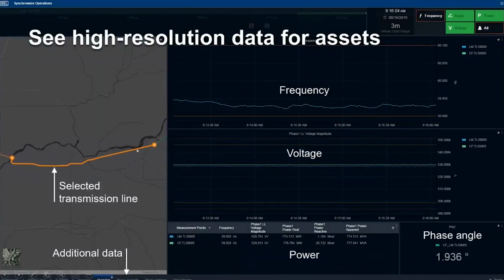So you can see that once I click on that asset, it's giving me the frequency, the voltage, the power, the phase angle, and any other information that I desire. Any information that the relay provides me, I can get that same information from this software. And again, it's in real time, it's in high resolution, so you can get much more information from this software and make better decisions or control your system in a better way to reduce the risk of wildfires.